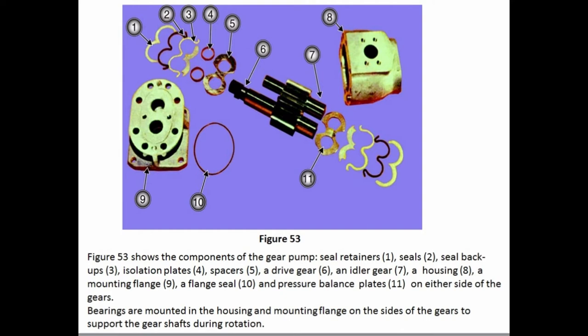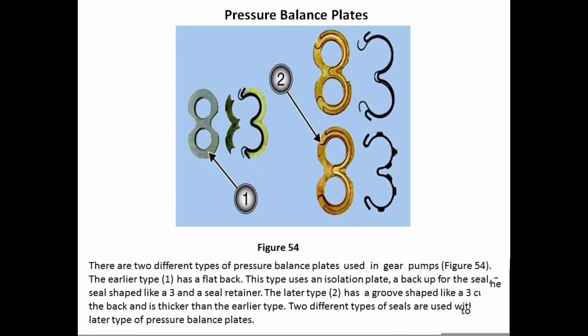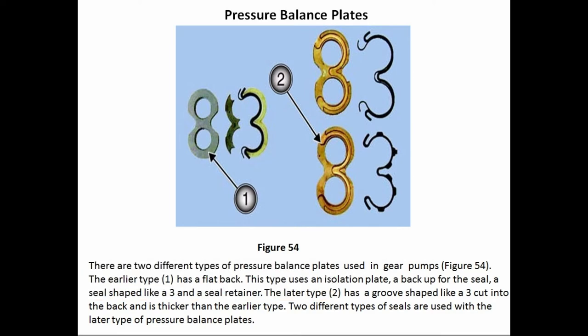Figure 53 shows the components of the gear pump: seal retainers (1), seals (2), seal backups (3), isolation plates (4), spacers (5), a drive gear (6), an idler gear (7), a housing (8), a mounting flange (9), a flanged seal (10), and pressure balance plates (11) on either side of the gears. Bearings are mounted in the housing and mounting flange on the sides of the gears to support the gear shafts during rotation. There are two different types of pressure balance plates used in gear pumps (Figure 54): the earlier type has a flat back and uses an isolation plate, a backup, a seal shaped like a figure-3, and a seal retainer. The later type has a groove shaped like a figure-3 cut into the back and is thicker than the earlier type.